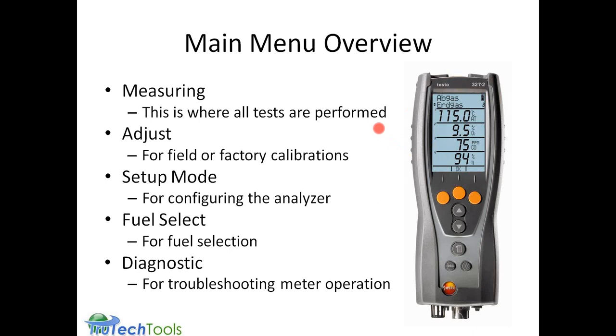And the diagnostic mode for troubleshooting any functions of the meter. It would tell you what sensors, what kind of error codes have been logged. This is part of that smart process that the meter has built into it, so you can share that with whoever you're taking your unit to for service, or make a phone call to them to ask what's happening in the meter. If I'm not mistaken, it also has the ability to print out the error screen, so you don't even have to tell somebody what it is. You could fax or scan it over to them. It would print out all the error codes. You could send it right to the printer, the optional printer.